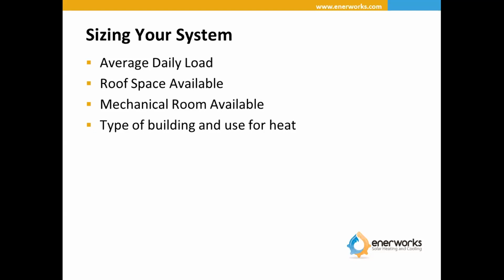And the type of building is important. If it's a building that has a commercial pool that you're heating, that's a very constant load. But if it's a dormitory, there might not be any load in the summer. In Canada, we've got ice skating arenas, and they're only going to be open in the winter. So it's really important to know what the load profile of the building is, because there are some cases where solar thermal may not be the best choice for that type of application.